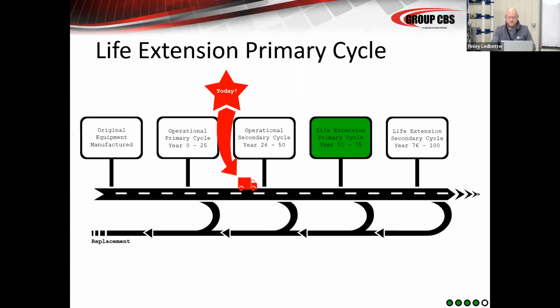But like I said earlier, the best way to do it is open it up, put your human eyes on it, and look for the telltale signs of insulation erosion. And when we get into the MTS section, which is the 3rd installment on this series, we're going to talk about that in great detail. In the 4th installment, we're going to talk about non-destructive and online testing techniques that will help you to get to those problem areas without having to remove those panels. I don't suggest it. Certainly, if the equipment's been in service 50 years, 75 years, 100 years, I hope you've looked at every inch of it a few times.